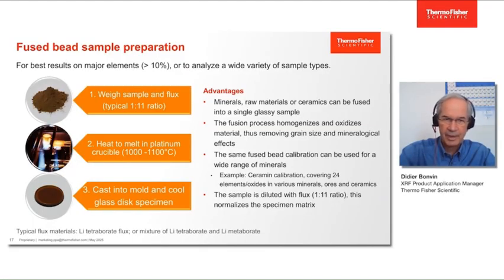So typically when we are above 10%, the effect is really quite big, and less so when we are below 10%, from 1 to 10%. One of the disadvantages, of course, is that we are going to dilute the sample. Typical ratio is one part sample and 11 parts flux. The flux being a mixture of lithium tetraborate and lithium metaborate, typically.